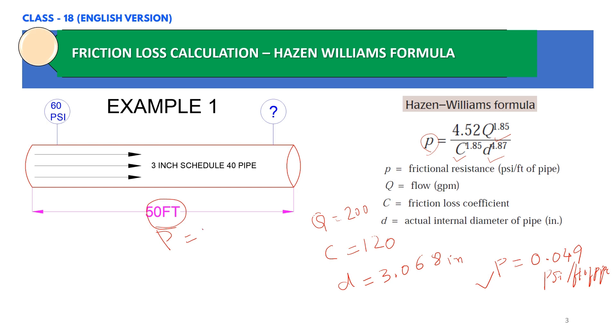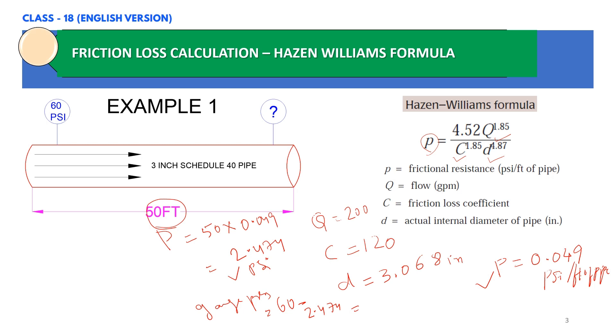The actual friction loss for the complete 50 feet of pipe is 50 multiplied by 0.049, which gives 2.474 PSI. The gauge pressure at the end will be the initial pressure of 60 PSI minus the friction loss of 2.474 PSI, giving a pressure gauge reading of 57.526 PSI.